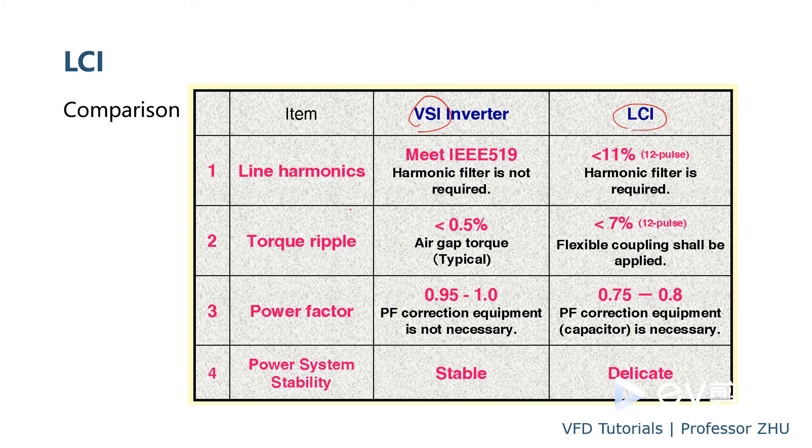Here's some comparison between the VSI and the LCI. LCI actually is an older technology and is used very few today. In some very few applications to use LCI, such as a huge drive for the pump or blower system, especially for the soft starting, like on the blower for the steel mill. And the drive is only used to start the motor. And after the start, it will be synchronized to the grid and run by the grid. So the driver is only running for a short period of time. So harmonics is not a big issue. And the LCI is cheap.